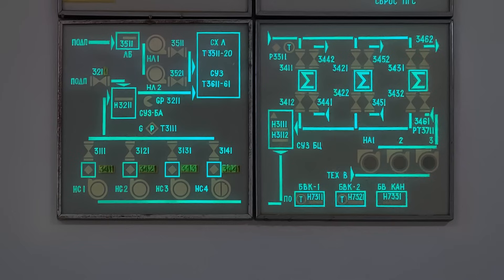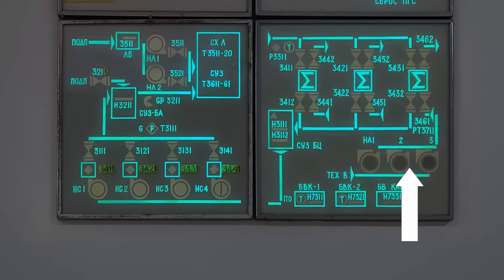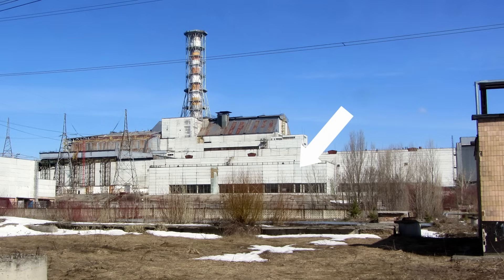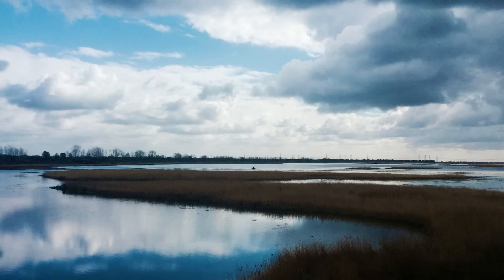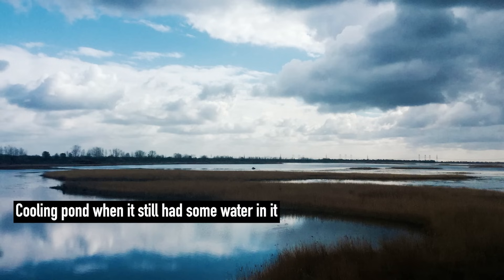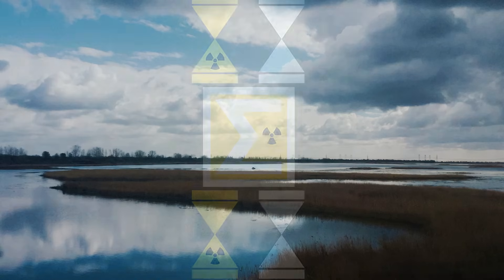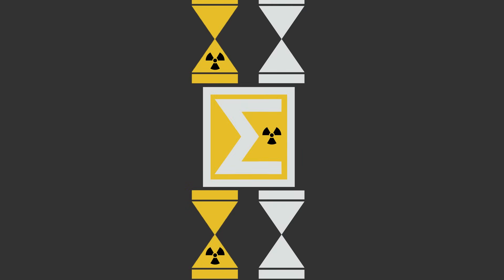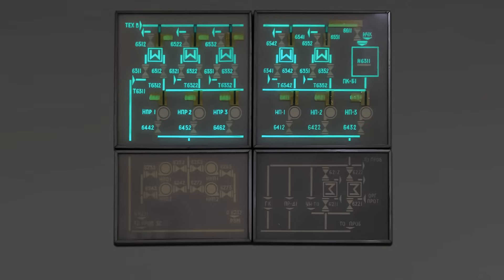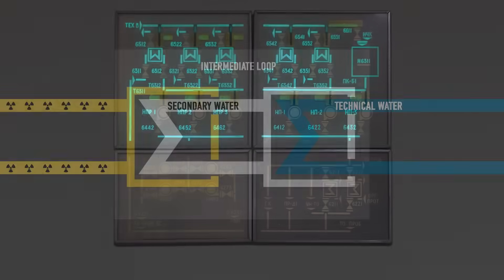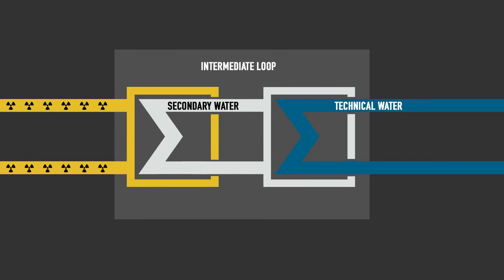These exchangers are cooled indirectly by technical water. Technical water comes from the cooling pond, pumped by these three large pumps. They are actually located in a separate building of the pumping station. Because this water never mixes with coolant after treatment and can return back to the pond. But there are loops with much more radioactive water inside. And I guess you can imagine what will happen if some pipe in some exchanger will break down. Basically all that will just go to the cooling pond polluting everything. So to avoid the chance of that, there is a so-called intermediate loop, a part of which is pictured here. It uses its own pumps to carry its water to cool those contaminated circuits. And only then this secondary water cooled using the water from cooling pond in extra exchanger of the intermediate loop. So it is much safer.